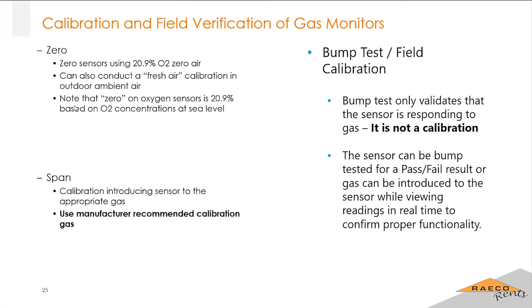All right. So for the zero calibration, you can use 20.9% oxygen, which is considered zero air. You can also just go outdoors and do what they call a fresh air calibration. Some people don't like to do that, but if you're outside and not near any industrial processes or anything like that, you're probably going to have pretty clean air, and so you can zero those sensors outdoors. And then we do the span calibration, which is running a certain concentration of gas across the sensor. Ideally, you're using the manufacturer's recommended calibration gas.